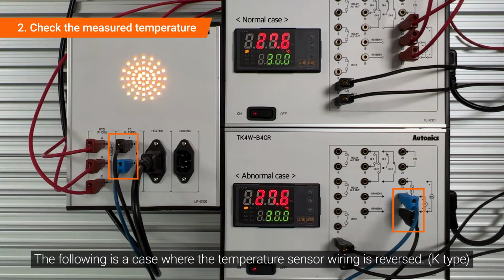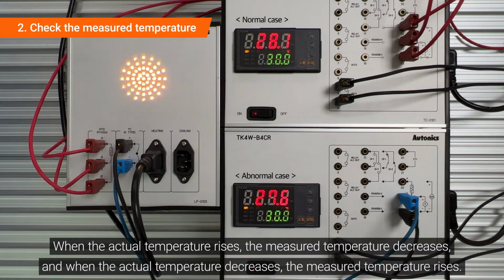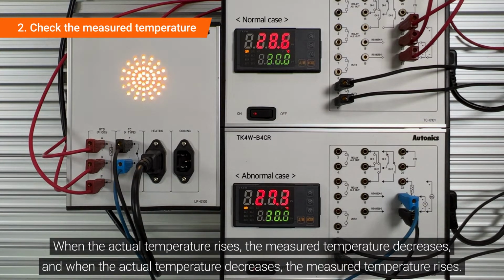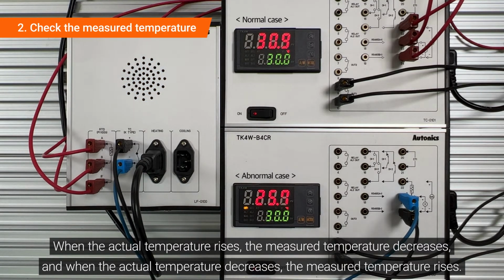The following is a case where the temperature sensor wiring is reversed. When the actual temperature rises, the measured temperature decreases. And when the actual temperature decreases, the measured temperature rises.